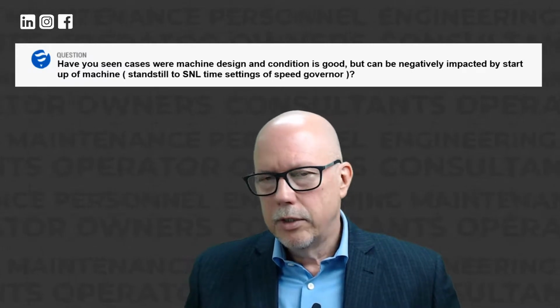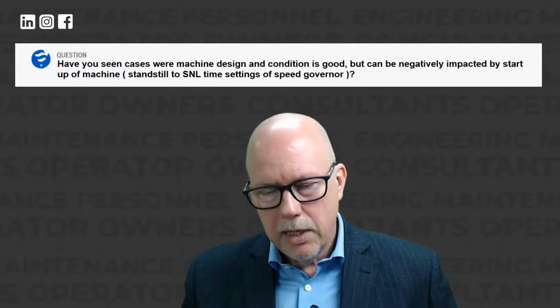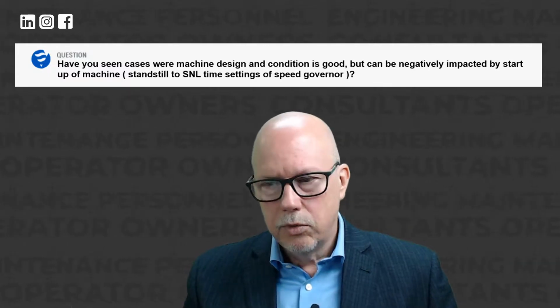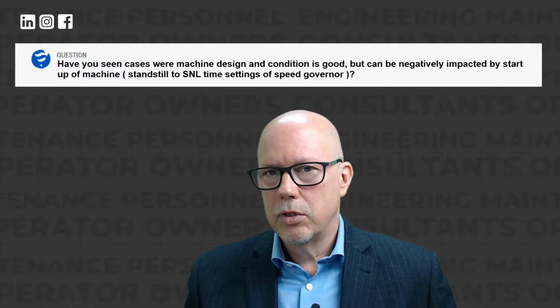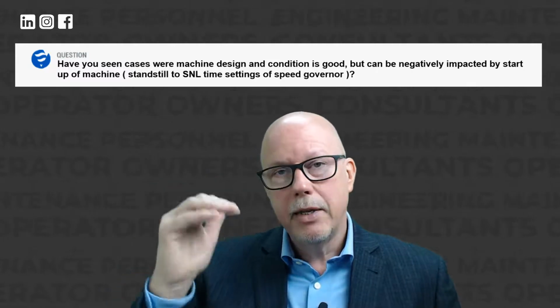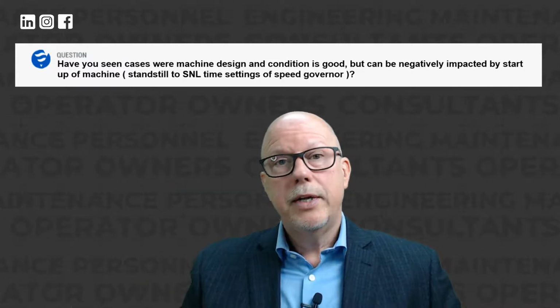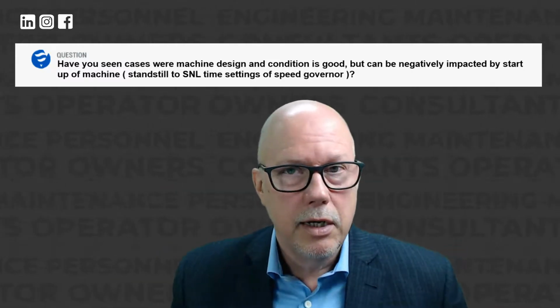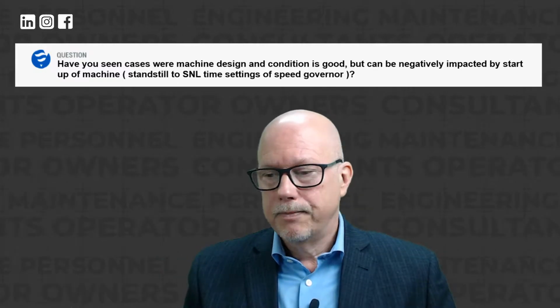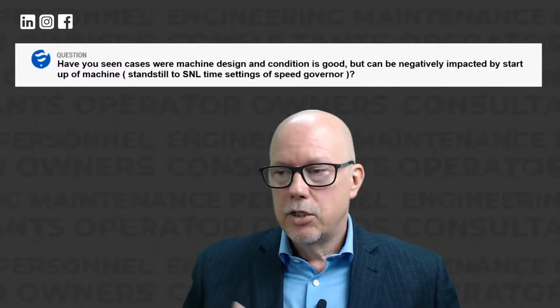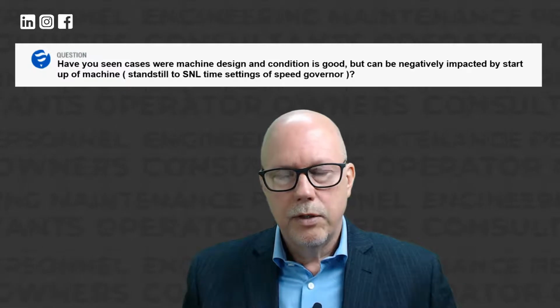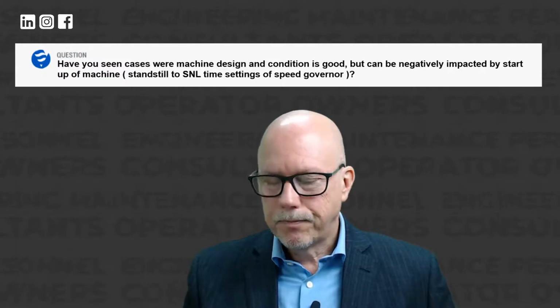The utility said, okay, we'll buy into your design, but you will put 16 air gap sensors on each of the stators, 8 at the top and 8 at the bottom, so we can validate that your design works as promised. So they did, and I actually went to site for the original commissioning.